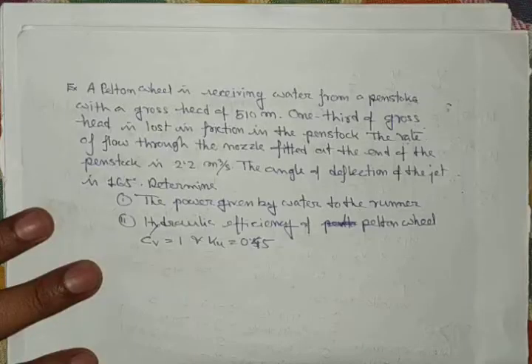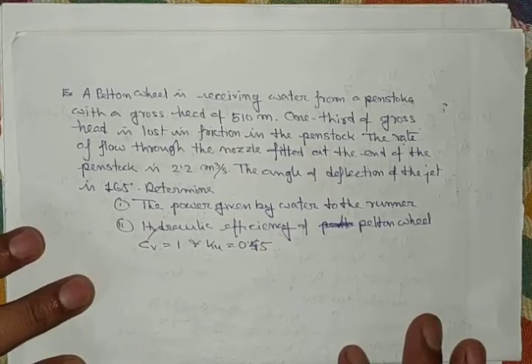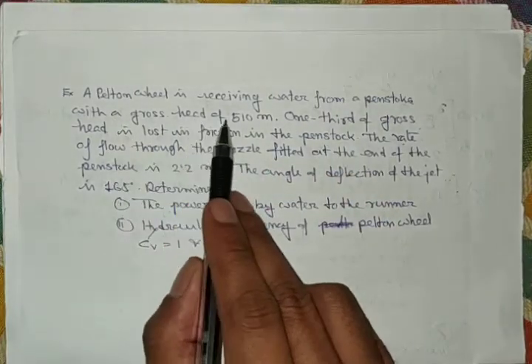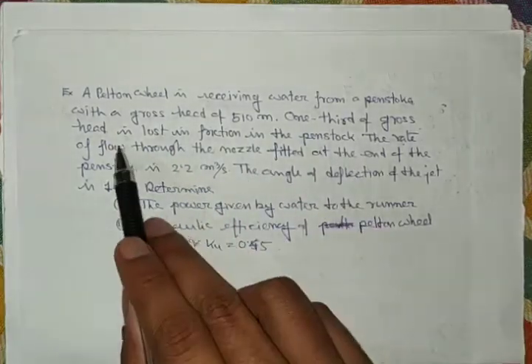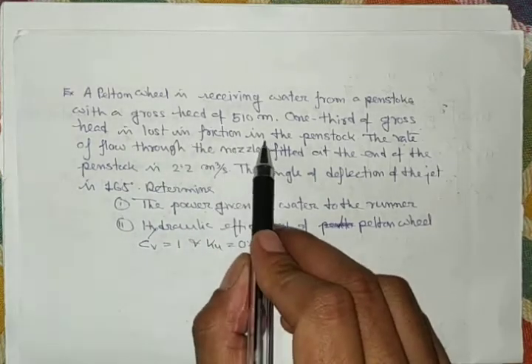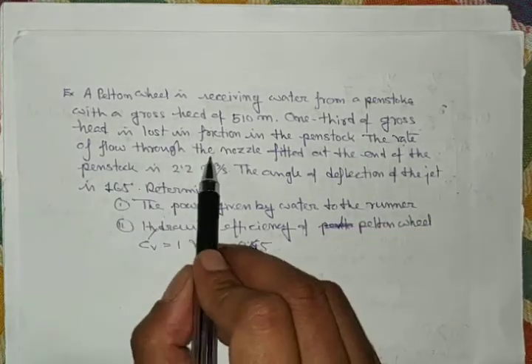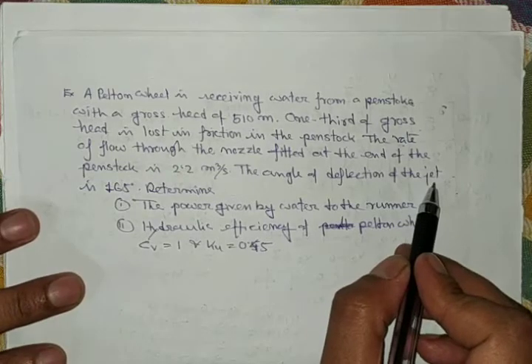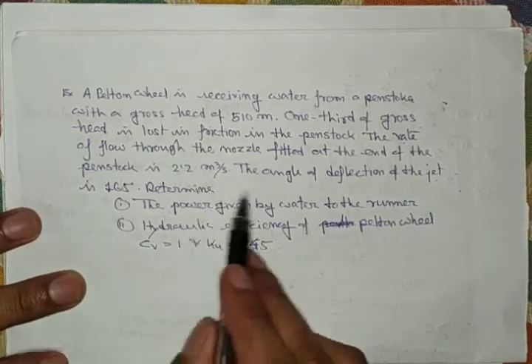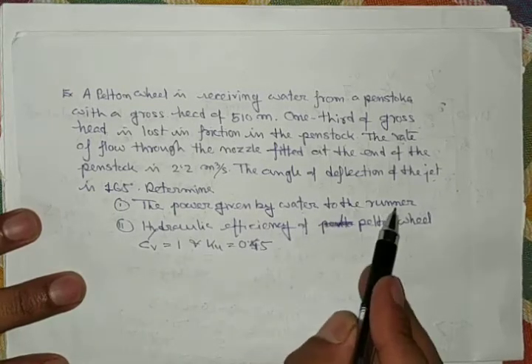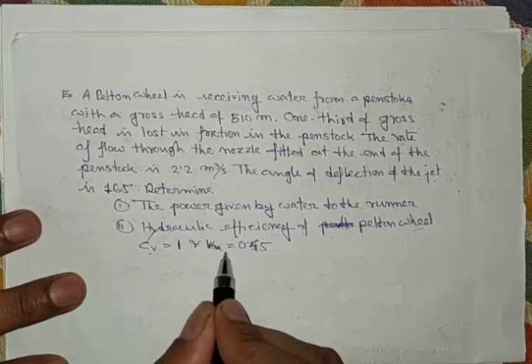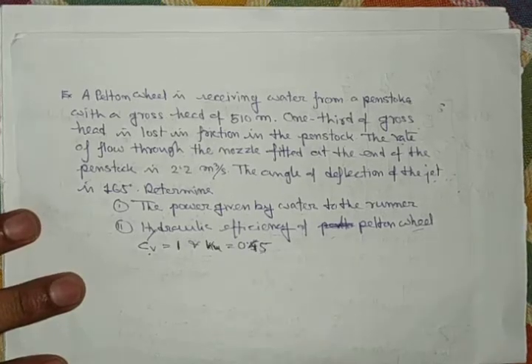Dear students, today we will discuss a few numericals on Pelton wheel. A Pelton wheel is receiving water from a penstock with a gross head of 510 meters. One third of the gross head is lost in friction in the penstock. The rate of flow through the nozzle is 2.2 m³/s, the angle of deflection of the jet is 165°. Determine power given by water to the runner and hydraulic efficiency, if Cv=1 and speed ratio Ku=0.45.